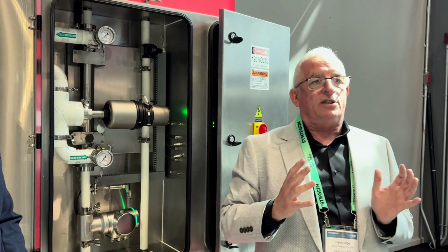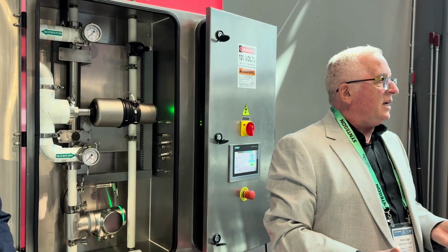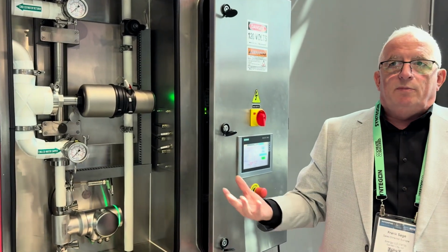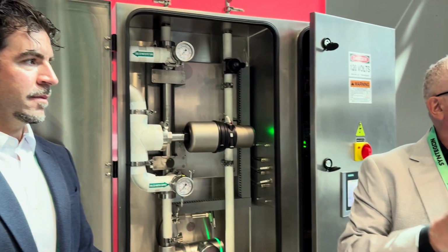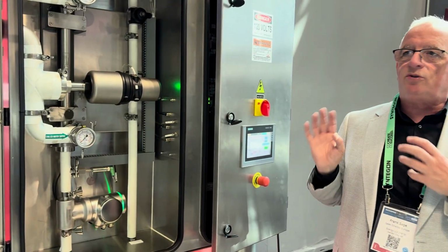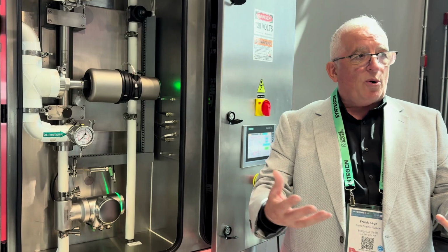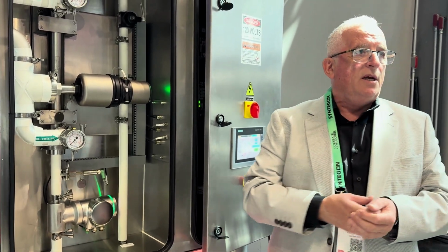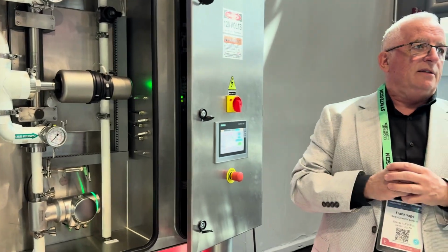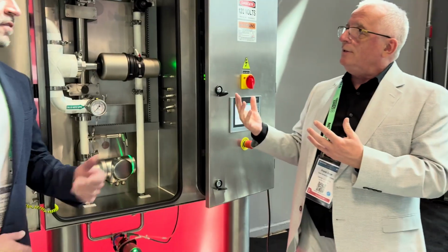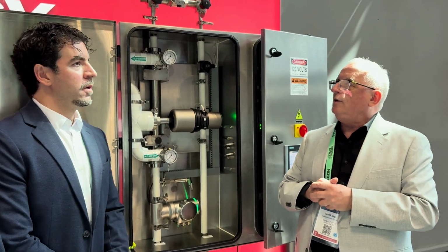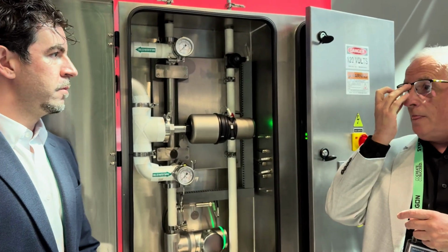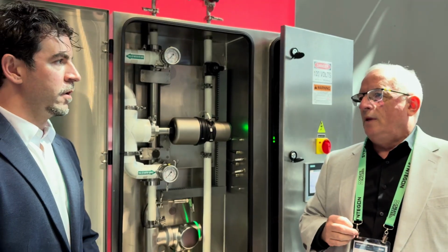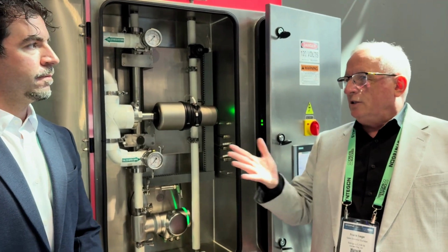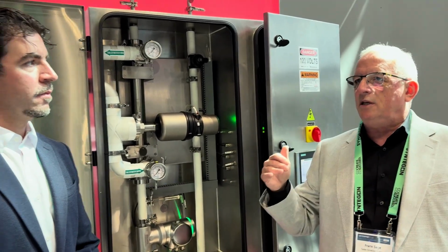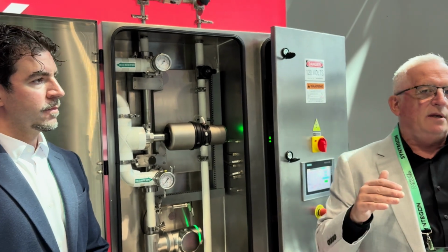But on that chromatography application, when somebody goes to buy a chromatography skid, they're spending a couple of million, maybe more, depends on the scale. The massive challenge they have is, how do I now supply the most critical utility to this exceptionally important and expensive piece of process equipment? We say to them, let us take care of that. And we do. Well, that's the cost of the product itself. Yes, it could be in the millions per batch. It's very critical to nail the temperature and have really accurate control when it comes to the temperature of the WFI. Absolutely.